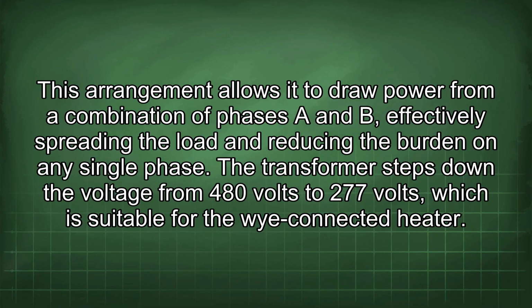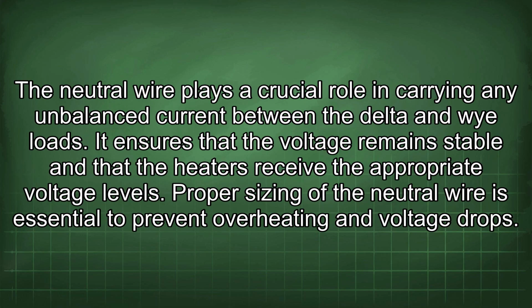The transformer steps down the voltage from 480 volts to 277 volts, which is suitable for the Y-connected heater. The neutral wire plays a crucial role in carrying any unbalanced current between the Delta and Y loads. It ensures that the voltage remains stable and that the heaters receive the appropriate voltage levels. Proper sizing of the neutral wire is essential to prevent overheating and voltage drops.